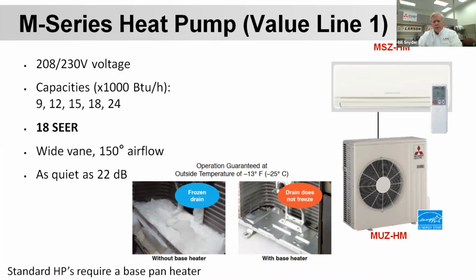Now, also, I wanted to mention, this is the standard heat pump. This is not a hyperheat pump. All standard heat pumps, non-hyperheats, do not come with a base pan heater. The base pan heater sits in the bottom tray here. It would sit right in this area here. Without it, you build up ice and freeze, and the ice can actually crush the bottom coil here. So you'd have to add a base pan heater in our standard heat pump models.